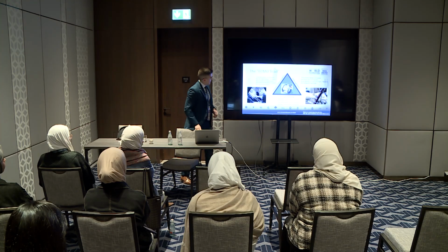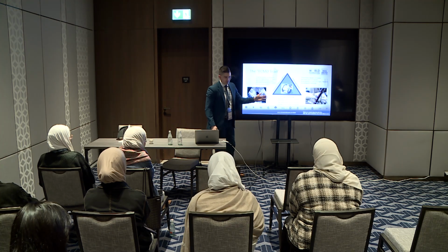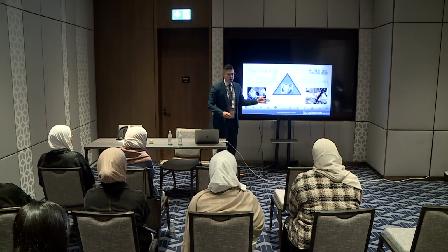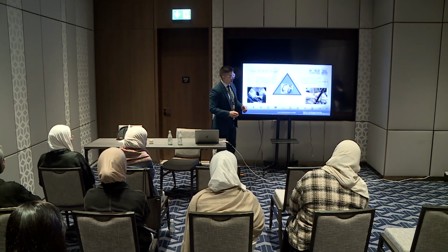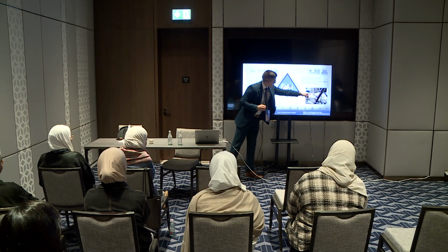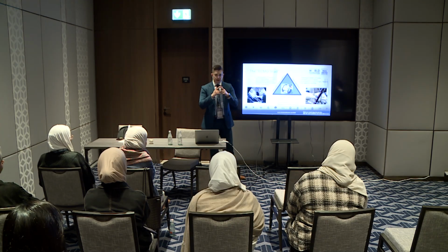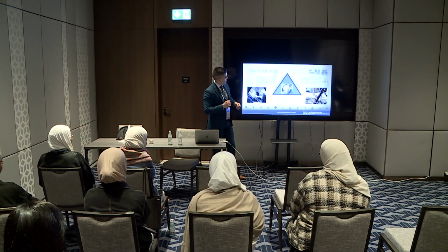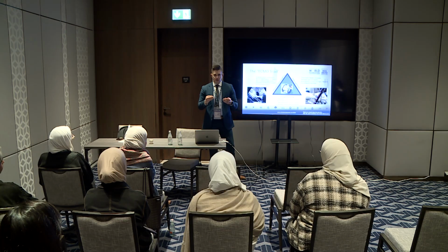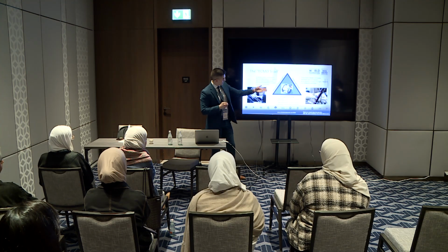Unique to ECMO, and quite different from hemodialysis, there are places where we can have turbulent blood flow. Turbulent blood flow is where the flow is not laminar, so something is disrupting laminar flow. Usually in ECMO, this is places where we have connectors. We may have a Y-site connector where we're bridging two lines together, or really anywhere that we have a connector that introduces a defect in the laminar flow. And when you have turbulence, you increase the risk of thrombosis. This can happen in the tubing, in the pump, in the oxygenator.